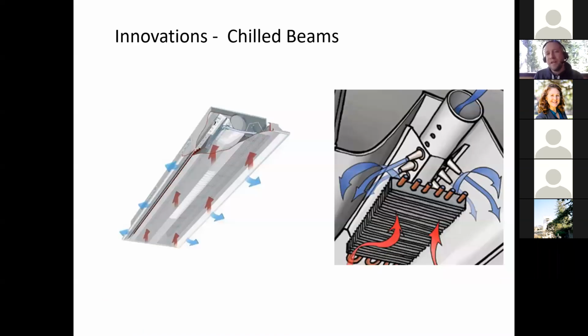So those nozzles shown on the right, you can see the fresh air, the ventilation air, is blowing really fast through there. And when we have very fast moving air, it's going to create a low pressure zone. And that's going to actually draw air from the room to try to fill that low pressure zone. So air from the room is going to get sucked over the heating or cooling coil, that thing in the middle, right here. And that air is trying to fill in the low pressure zone that's caused by those Venturi nozzles.